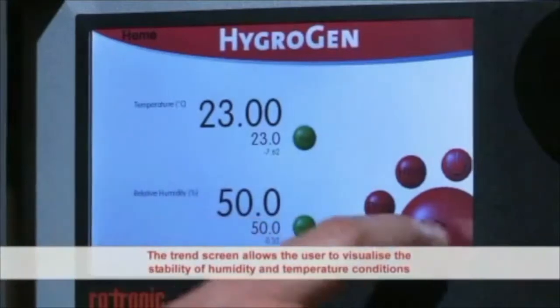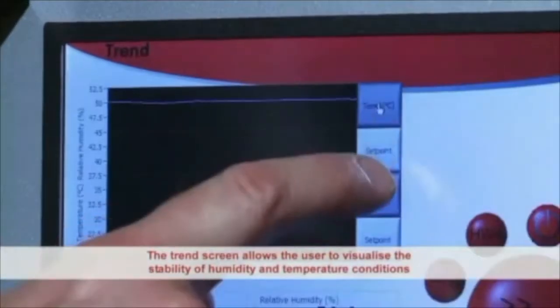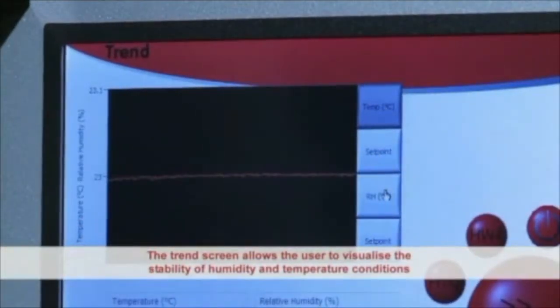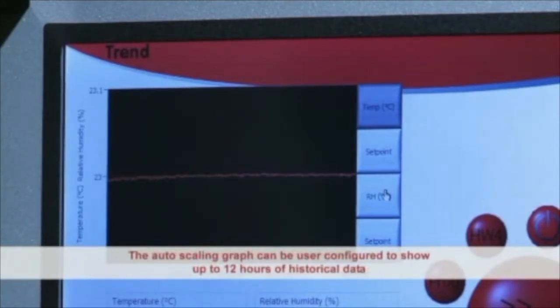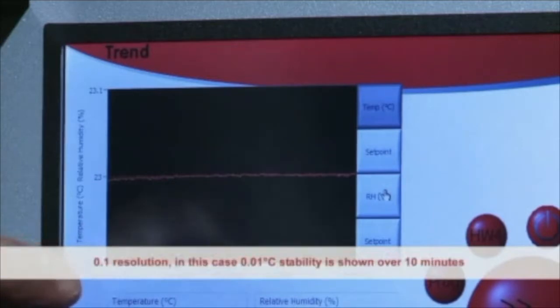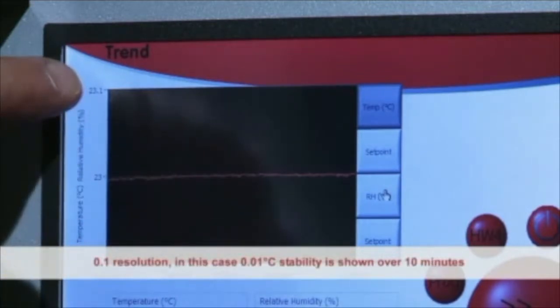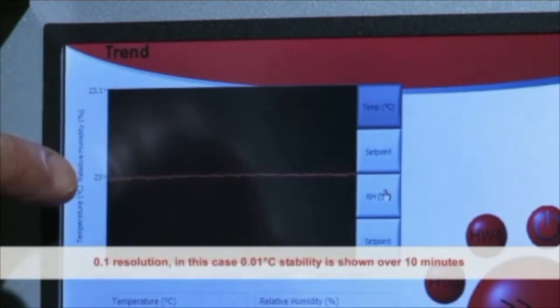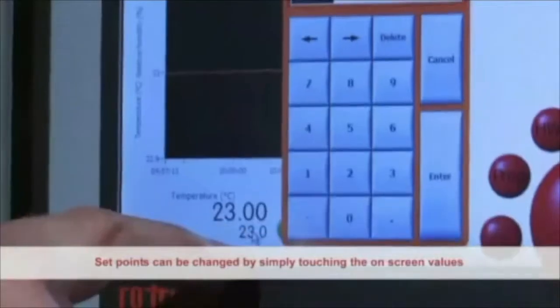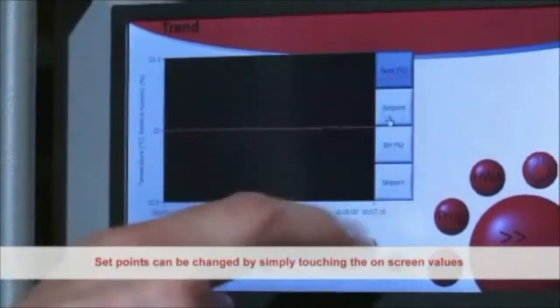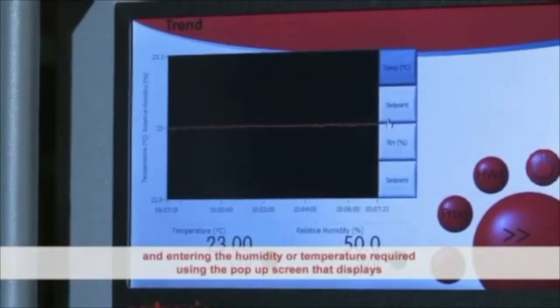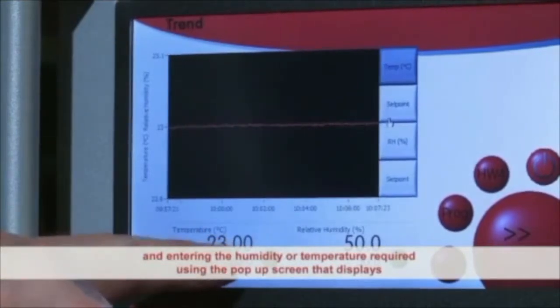The trend screen allows the user to visualize the stability of the humidity and temperature conditions. The auto-scaling graph can be user configured to show up to 12 hours of historical data. 0.1 degrees C resolution, in this case indicates 0.01 degrees C temperature stability. This is shown over a standard 10-minute period. Set points can be changed by simply touching the on-screen values and entering the humidity or temperature required using the pop-up screen that displays.